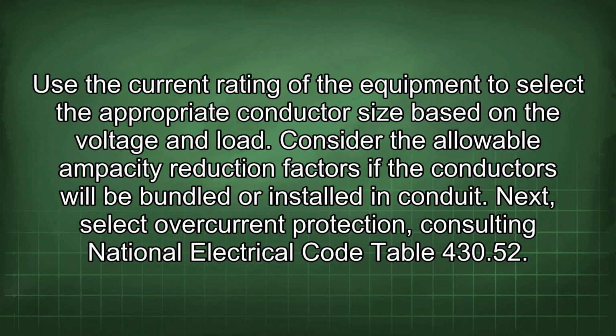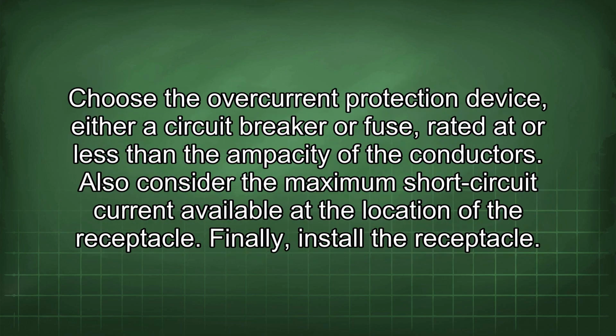Next, select overcurrent protection, consulting National Electrical Code Table 430.52. Choose the overcurrent protection device, either a circuit breaker or fuse, rated at or less than the ampacity of the conductors. Also consider the maximum short circuit current available at the location of the receptacle.